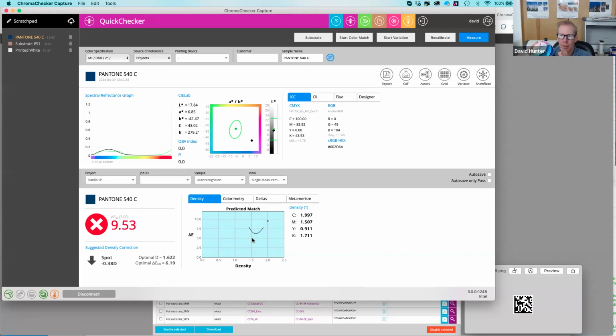So you make a chipbook for your ChromaSpot colors, I make one for mine. Our chipbooks will actually match really well, assuming that our instruments match really well, which ChromaChecker fixes too, because an i1 doesn't measure exactly the same as an Exact or a Nix or what have you. So these are all problems that ChromaChecker fixes to allow us to integrate color.